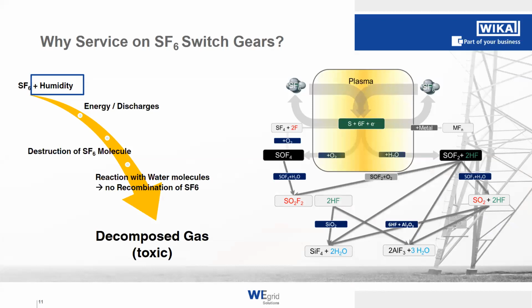Like I said, the humidity is one important factor, and that is because usually when we have pure SF6 and we introduce energy into our gas, the SF6 molecules are split. And if we don't have any other substances, any mixture within the gas, the SF6 molecules are able to fully recombine themselves. But with the introduction of humidity in our gas, the SF6 molecules are no longer able to fully recombine themselves and also develop decomposed gases, so byproducts.